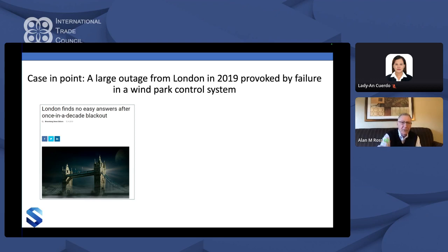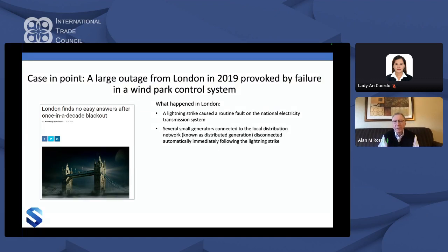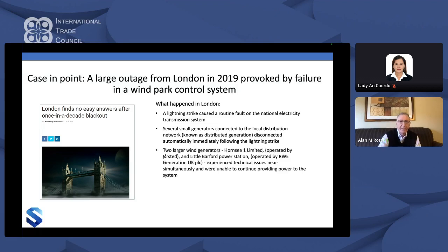Why? Because of this. What happened in London was a lightning strike caused a routine fault on the national transmission network. Routine - the fault gets reported, they route around it, everything works. But there were small generators connected at the local network. When that large fault happened and they tried to route around it and keep the generators running, they automatically became disconnected following the lightning strike. They should not have gotten disconnected, but they did.